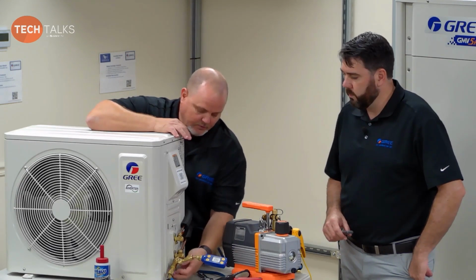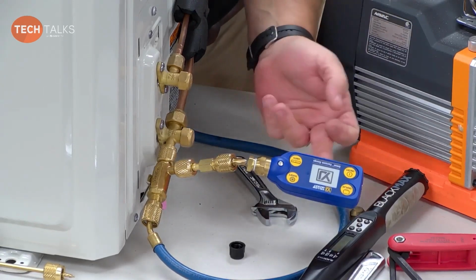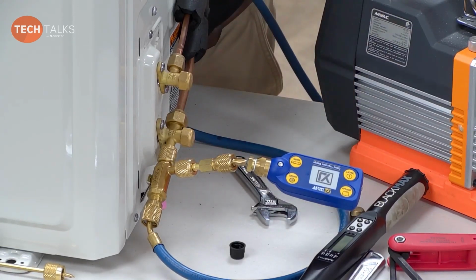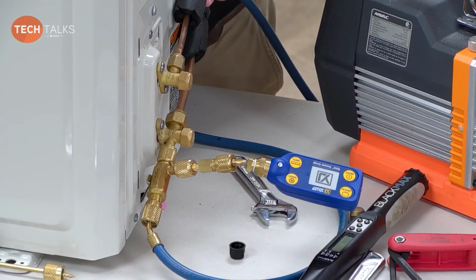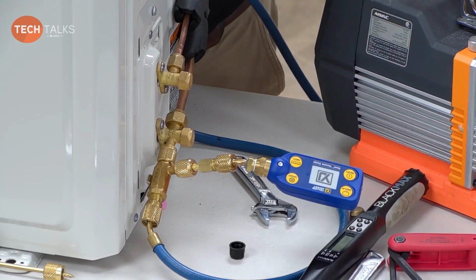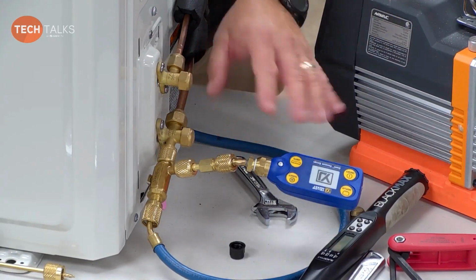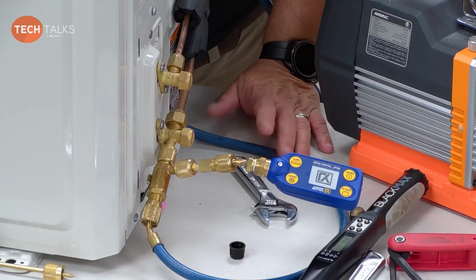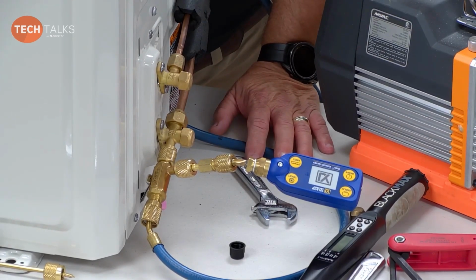The very first thing we're going to do is switch this off. Now the vacuum gauge is only reading the unit. Then if you want, you can turn your pump off and just let it sit. And we want to make sure it doesn't rise above 1,000 in 30 minutes. In 30 minutes is what we're looking for.